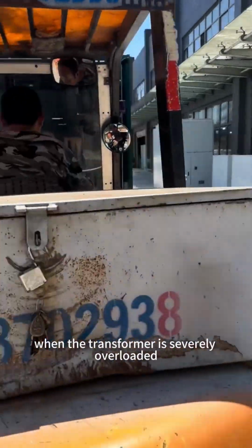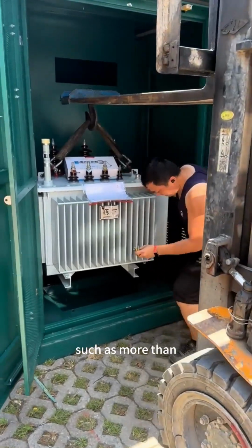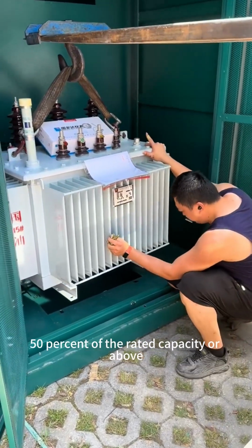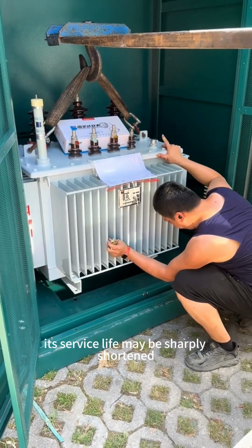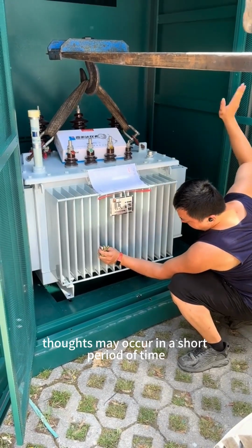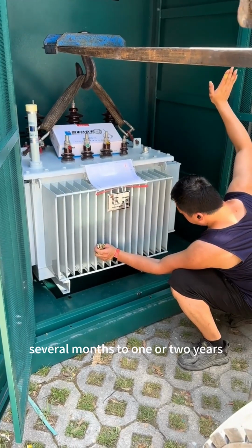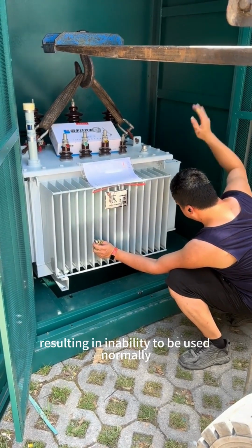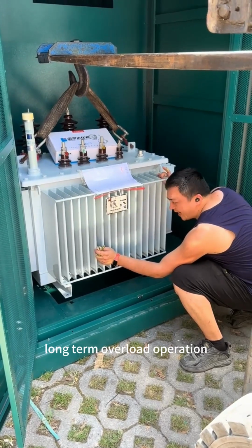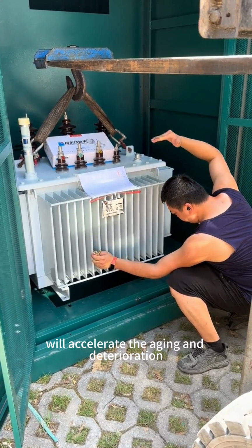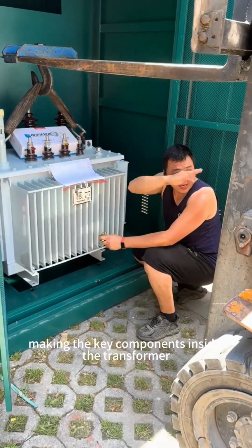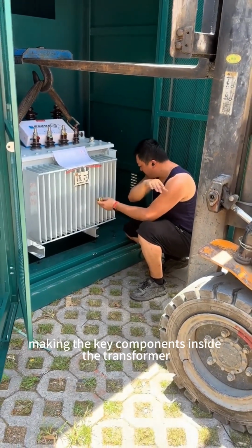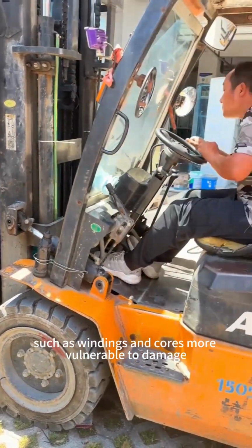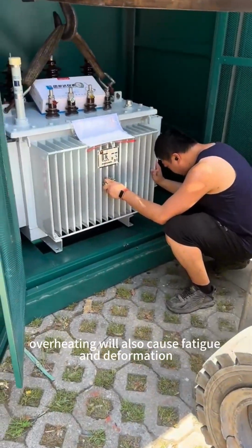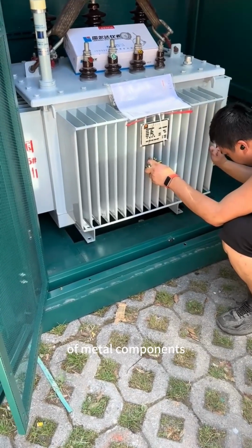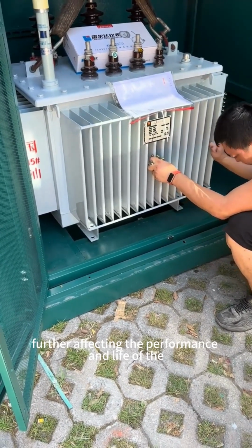When the transformer is severely overloaded, such as more than 50% above rated capacity, its service life may be sharply shortened, and serious faults may occur within a short period, from several months to 1 or 2 years, resulting in it being unable to be used normally. Long-term overload operation will accelerate the aging and deterioration of insulation materials, making key internal components such as windings and cores more vulnerable to damage. At the same time, overheating will cause fatigue and deformation of metal components, further affecting the performance and life of the transformer.